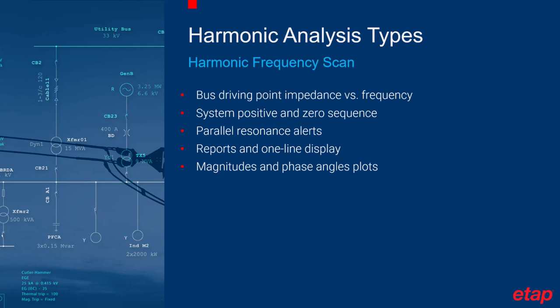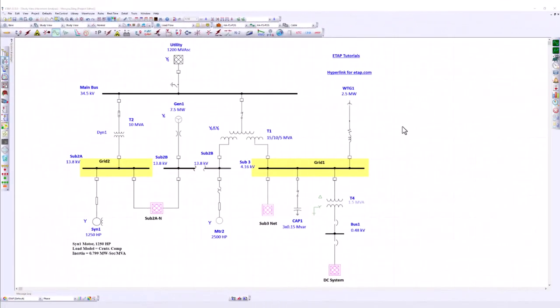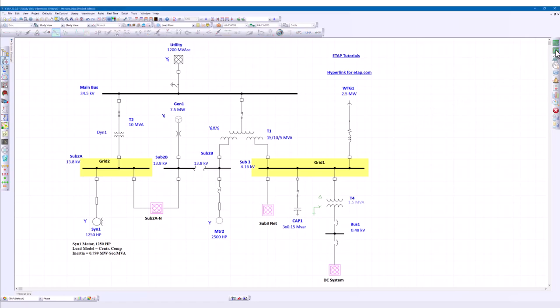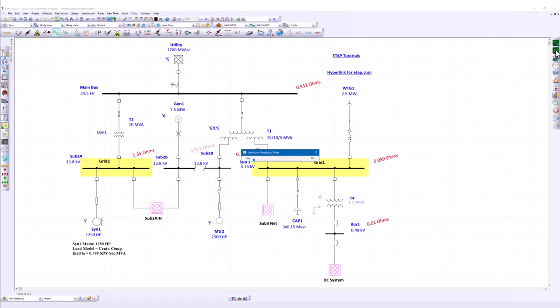Frequency scan uses system positive and zero sequence impedance as base impedance. The results are presented in reports, on the one-line diagram, as well as in the plots. Now let's see it in ETAP. The harmonic frequency scan analysis can be performed by clicking on the Run Frequency Scan button. After clicking on the button, you will see a harmonic frequency slider comes up.